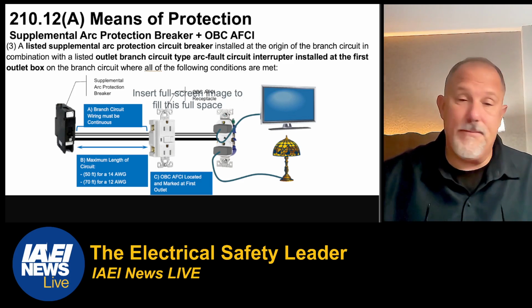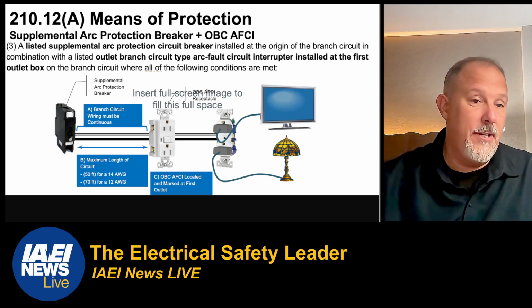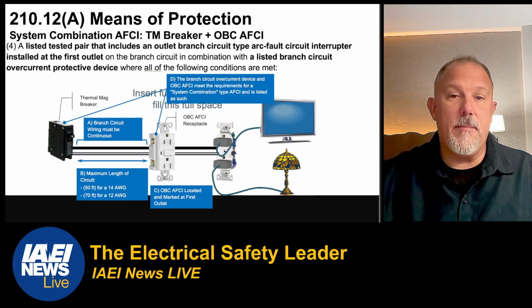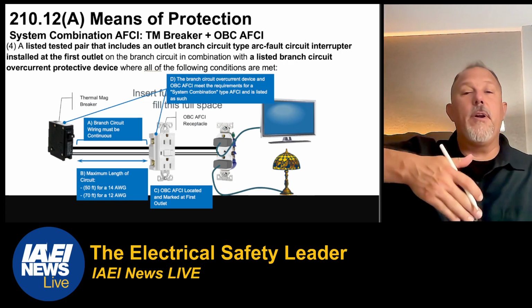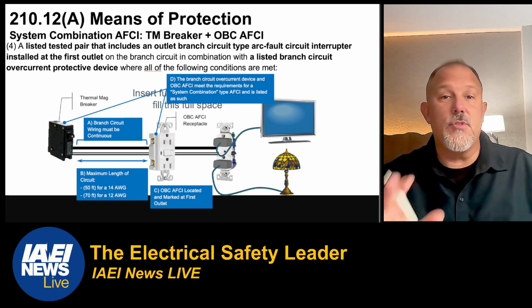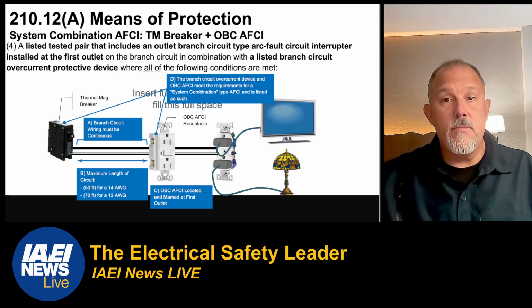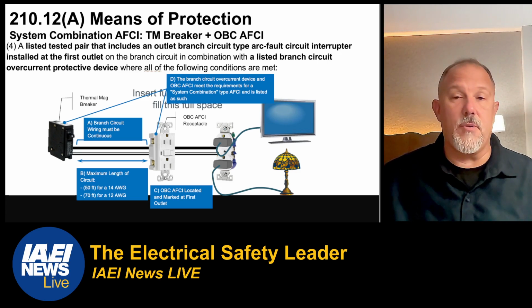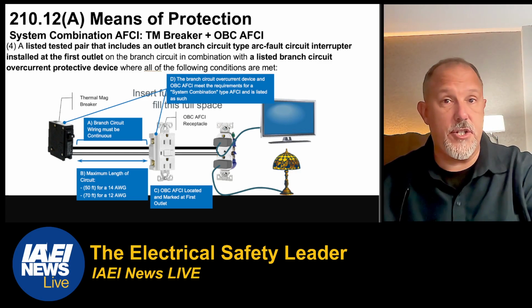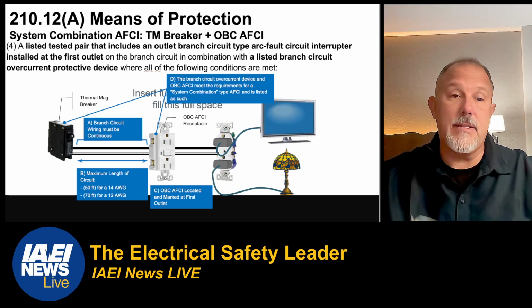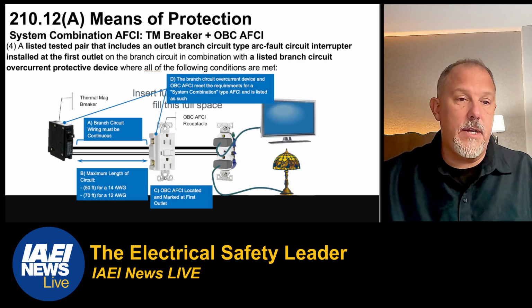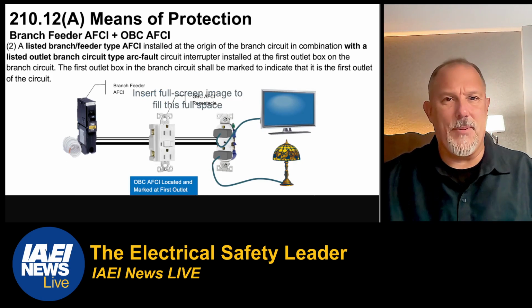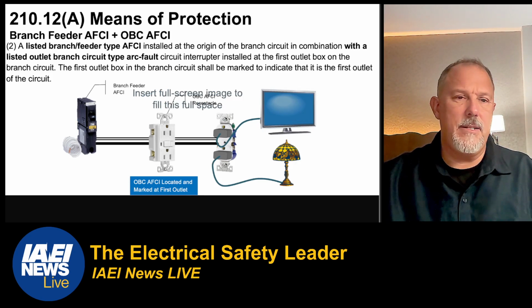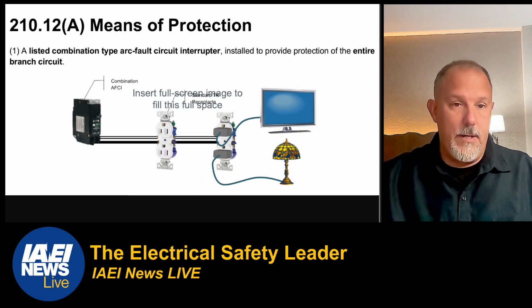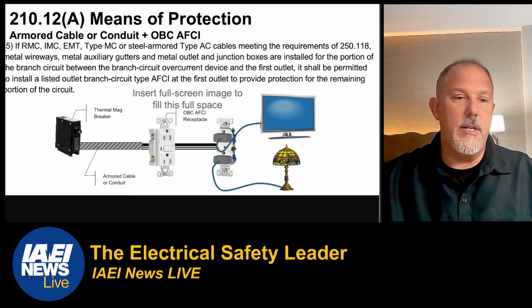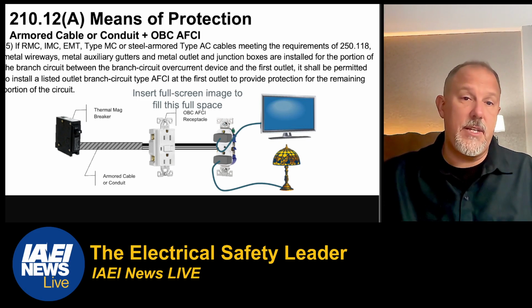And quite frankly, there's no supplemental arc protection. There's no standard for that product. The fourth is the system combination type AFCI with a thermomagnetic breaker plus an OBC AFCI. There is one manufacturer who's offering this listing. It's a listed pair that includes an outlet and a thermomagnetic circuit breaker combined to provide the equivalent protection of a UL 1699 device. So that product does exist on the market. 3 does not, 4 does. I would say it's kind of hard to find a branch feeder type AFCI. So I would say 2 doesn't make sense, but it's an option if you can find one. 1 is the readily available solution. And then there's 5 and 6. 5 is your RMC, so you're protecting the home run circuit.